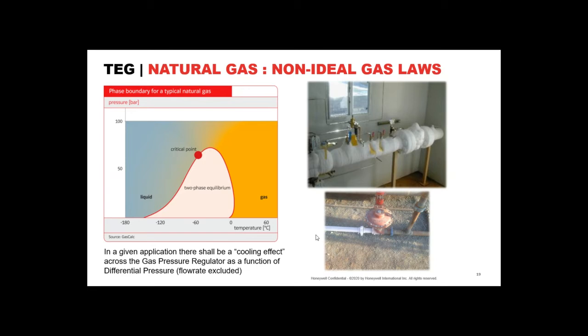So the regulator is a pressure reduction device, and quite often that reduction creates a temperature drop, and that drop is the Joule-Thomson effect. I don't need to discuss that one, it goes back to the 1800s. It's well known, well defined, plenty of math and proof out there. But basically, you drop the pressure. There's no exact rule of thumb, but a pressure drop gives a temperature drop, roughly, without the vast math.